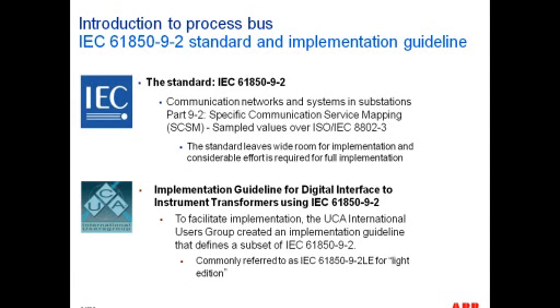So what are the standards that are really influencing sample values? There are really two documents that are important, or that are good references. The first one, of course, is the 9-2 part of IEC 61850, and there's a significant level of detail in this document in regards to the specific mapping of data onto an Ethernet ISO 8802-3 frame.